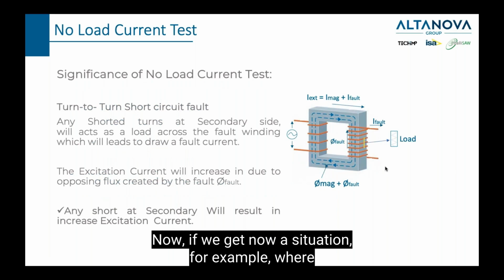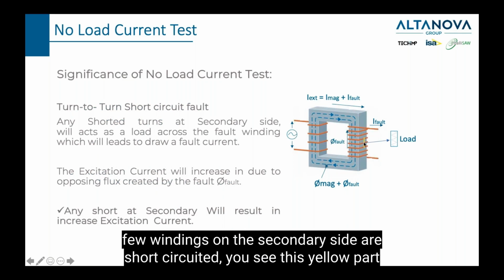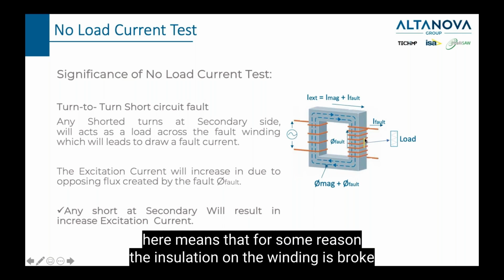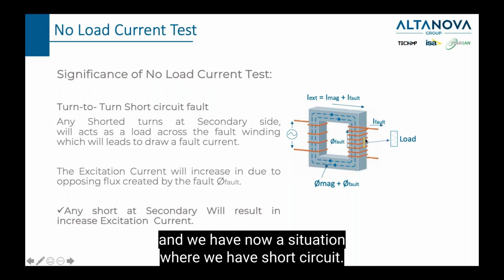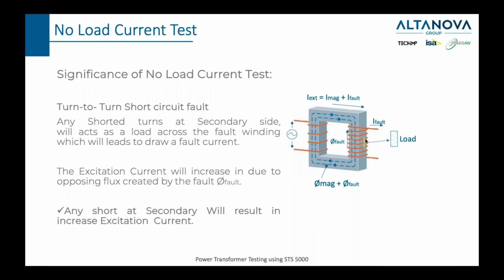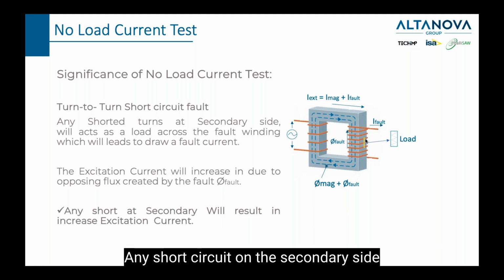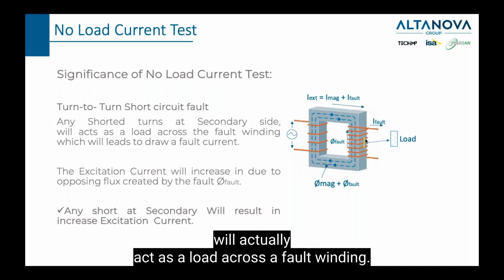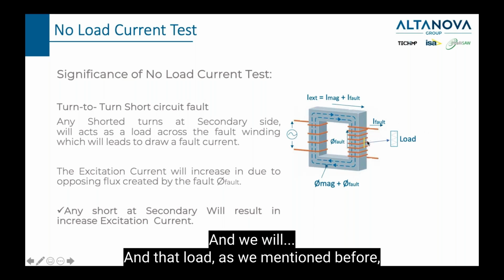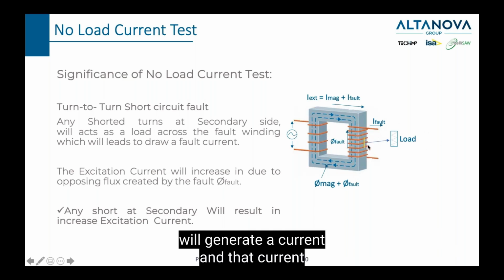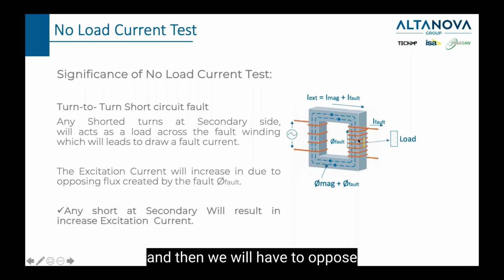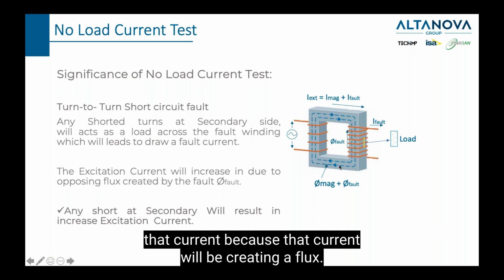Now, if we get a situation, for example, where a few windings on the secondary side are short-circuited. You see this yellow part here means that for some reason the insulation on the windings broke, and we now have a short circuit. Any short circuit on the secondary side will actually act as a load across a fault winding, and that load, as we mentioned before, will generate current, and then we will have to oppose that current because that current will be creating a flux.